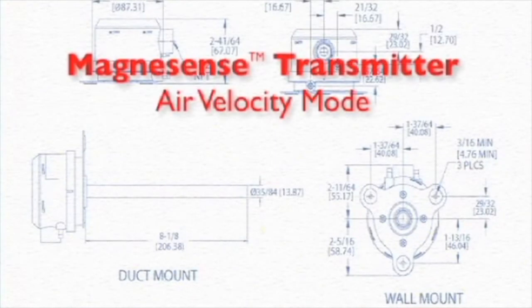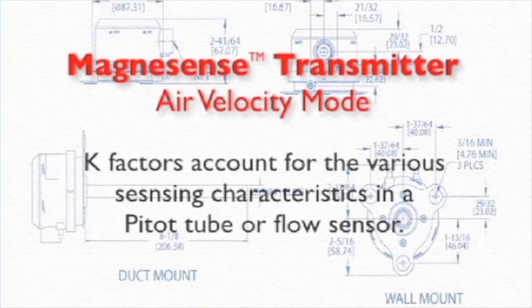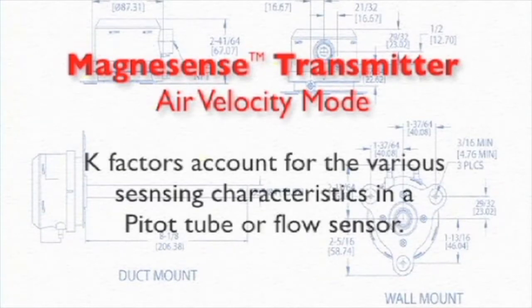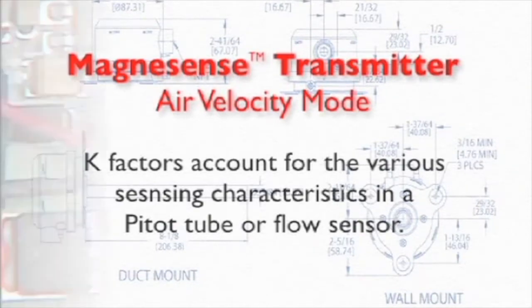When using various pitot tubes and flow sensors in this application, these sensors have various k-factors. These k-factors account for the various sensing characteristics of the flow sensor that may amplify or negate the actual velocity pressure being sensed. The Magnesense transmitter can account for these various k-factors.